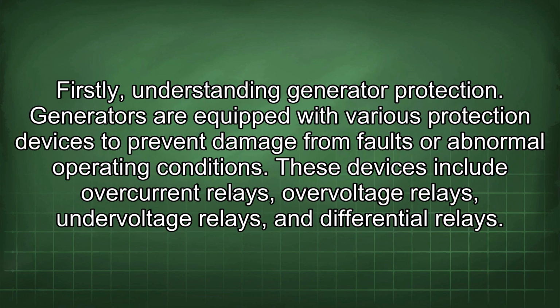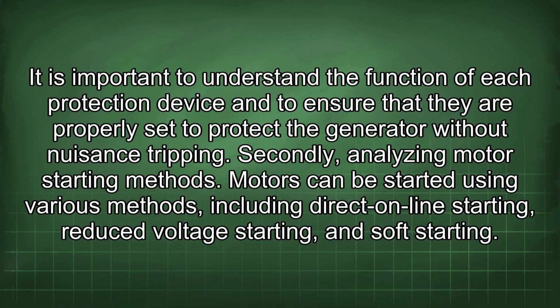Firstly, understanding generator protection. Generators are equipped with various protection devices to prevent damage from faults or abnormal operating conditions. These devices include overcurrent relays, overvoltage relays, undervoltage relays, and differential relays. It is important to understand the function of each protection device and to ensure that they are properly set to protect the generator without nuisance tripping.